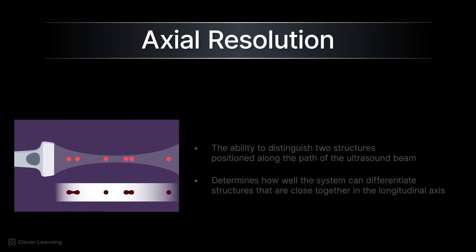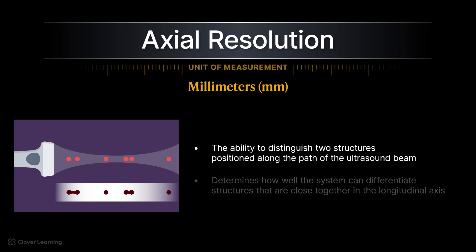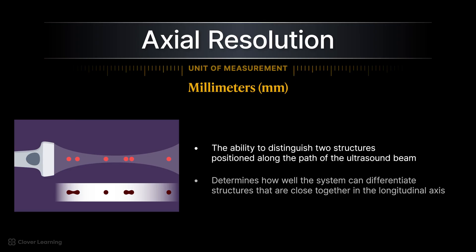Optimizing these resolution types collectively enhances diagnostic accuracy. Axial resolution is the ability to distinguish two structures positioned along the path of the ultrasound beam. This resolution is measured in millimeters and determines how well the system can differentiate structures that are close together in the longitudinal axis, meaning they are at different depths.